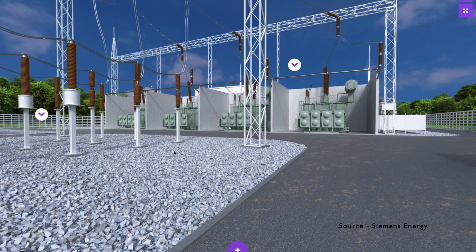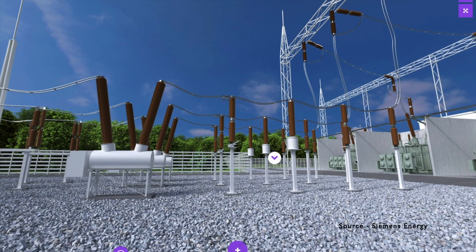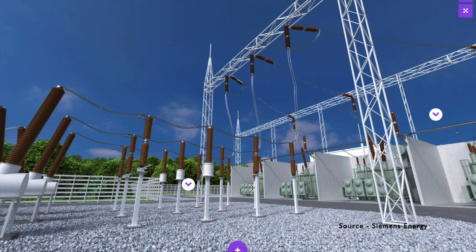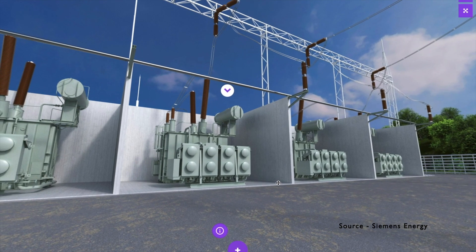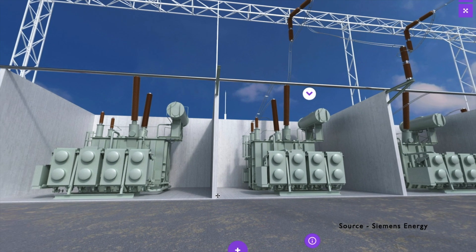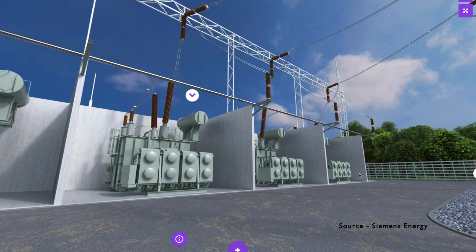This switchyard has everything: lightning arrestors, potential transformers, disconnectors, circuit breakers, current transformers. If necessary, AC filters can also be installed to filter out harmonic content in the AC supply voltage. Once everything is connected, that input is given to the converter transformers. The switchyard also protects the converter transformer, which is one of the most expensive and very bulky pieces of equipment. It makes a lot of noise when in operation — it is like an elephant, huge and bulky. Those converter transformers make the incoming supply suitable for the converting stations.